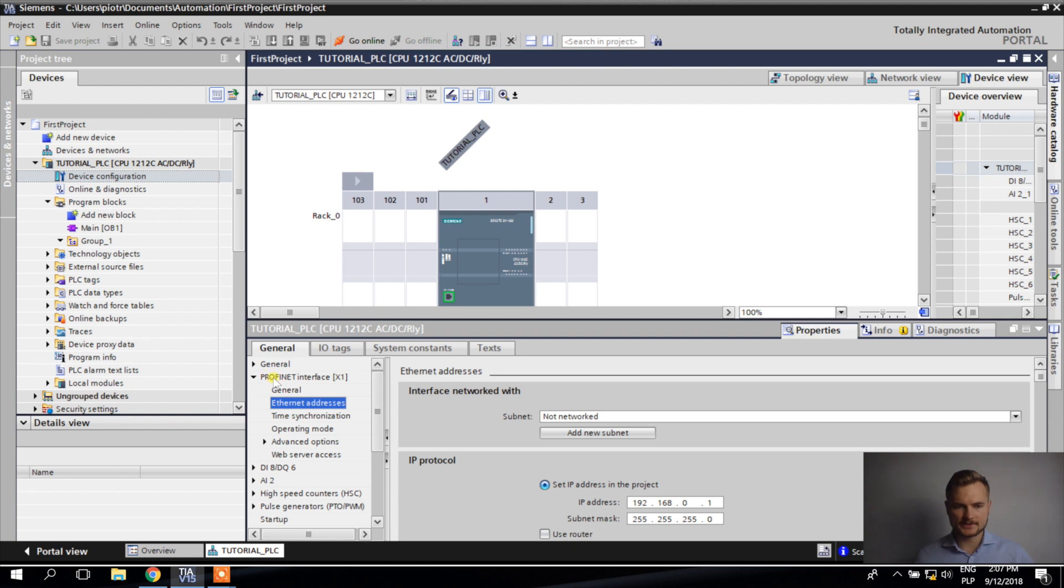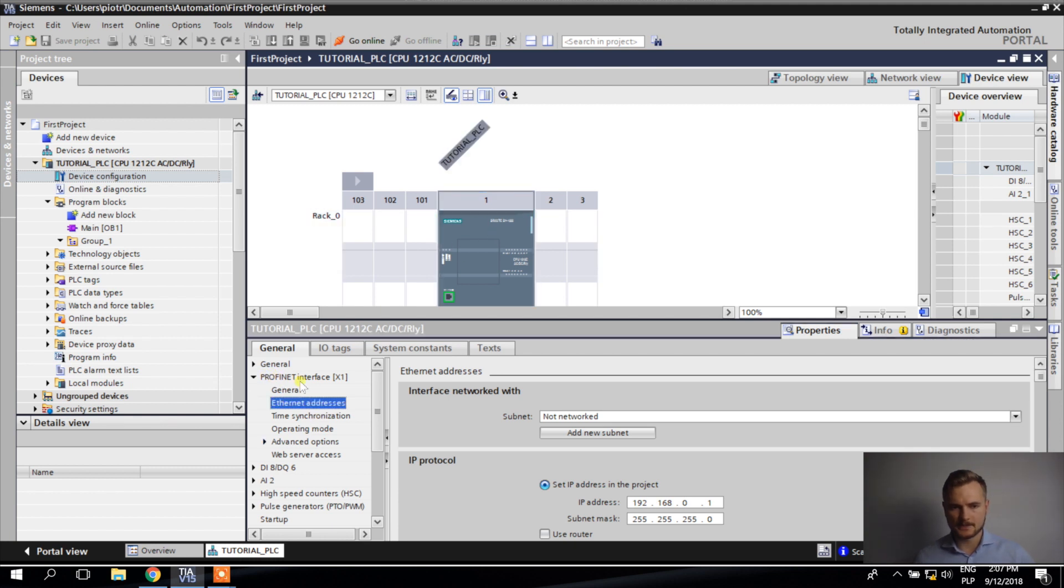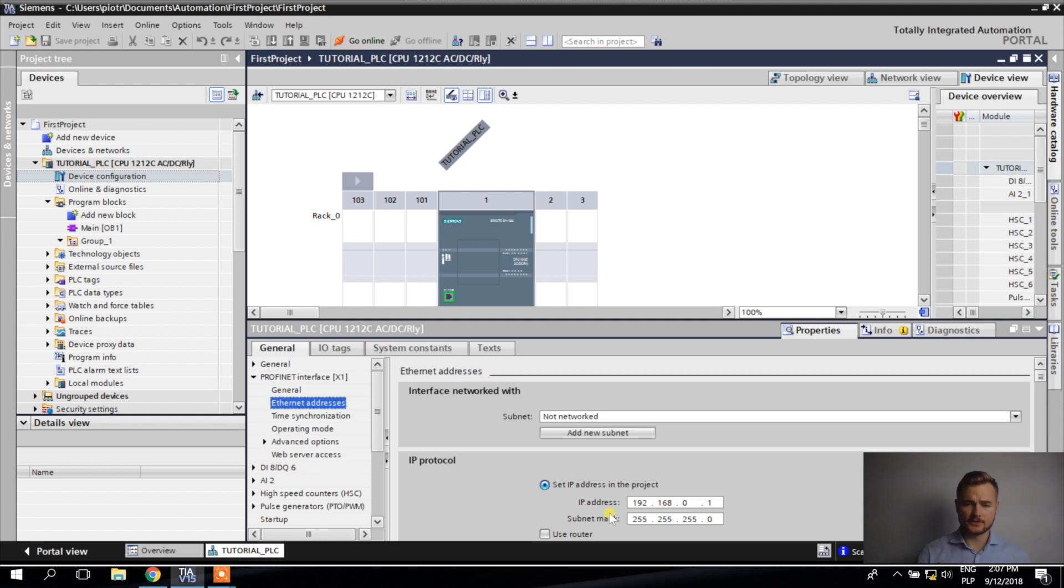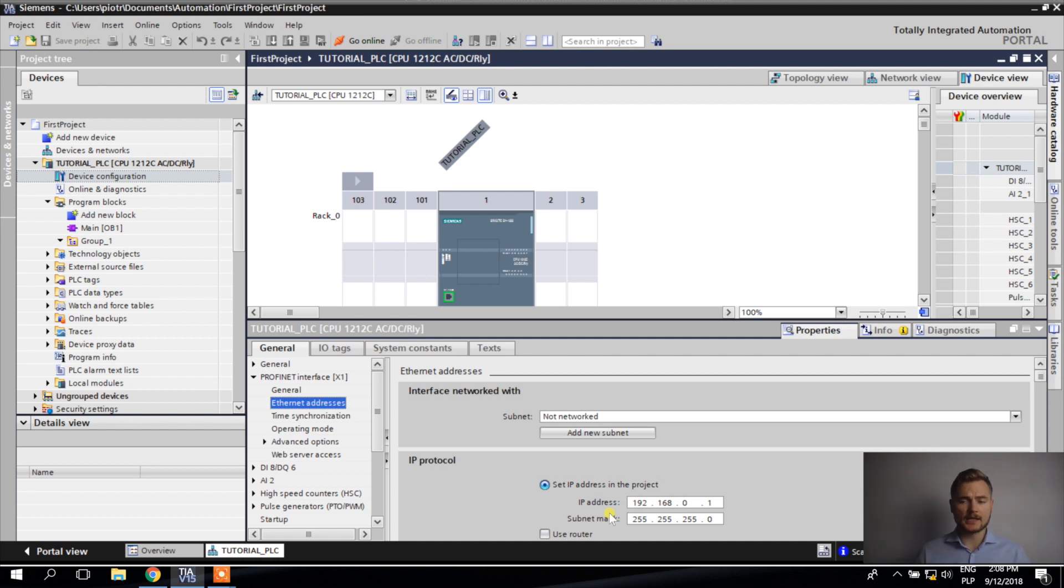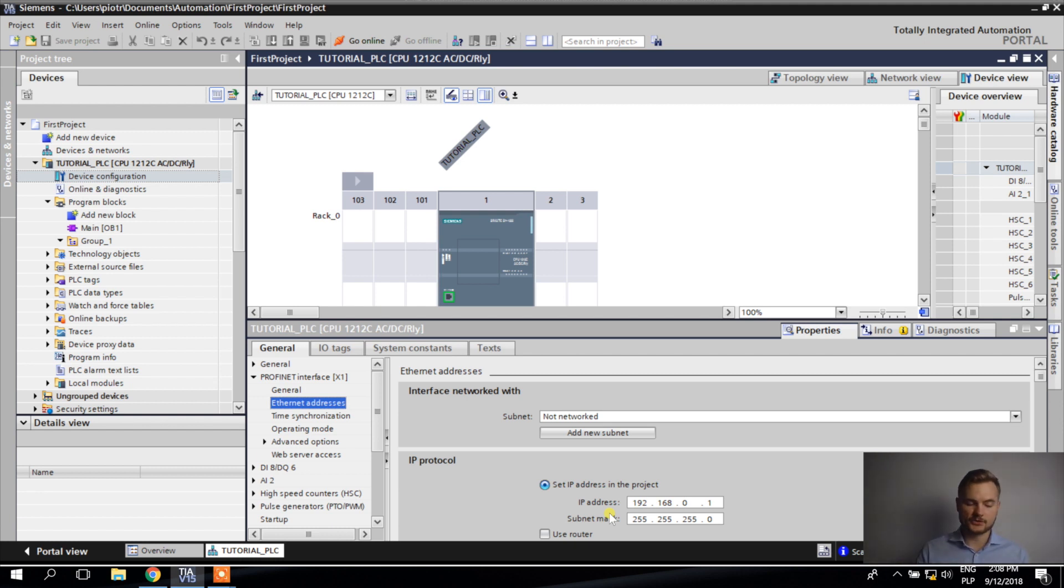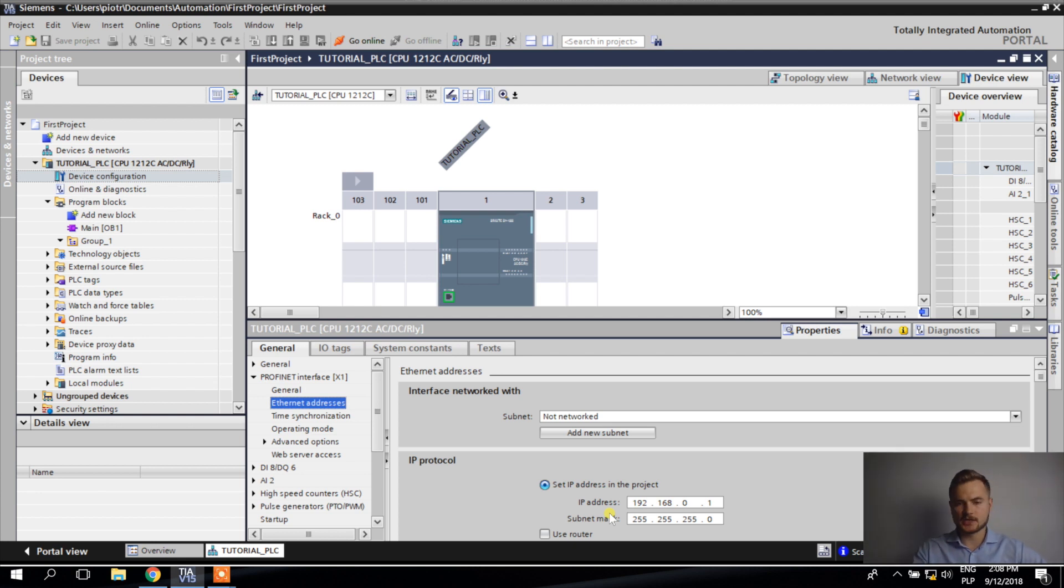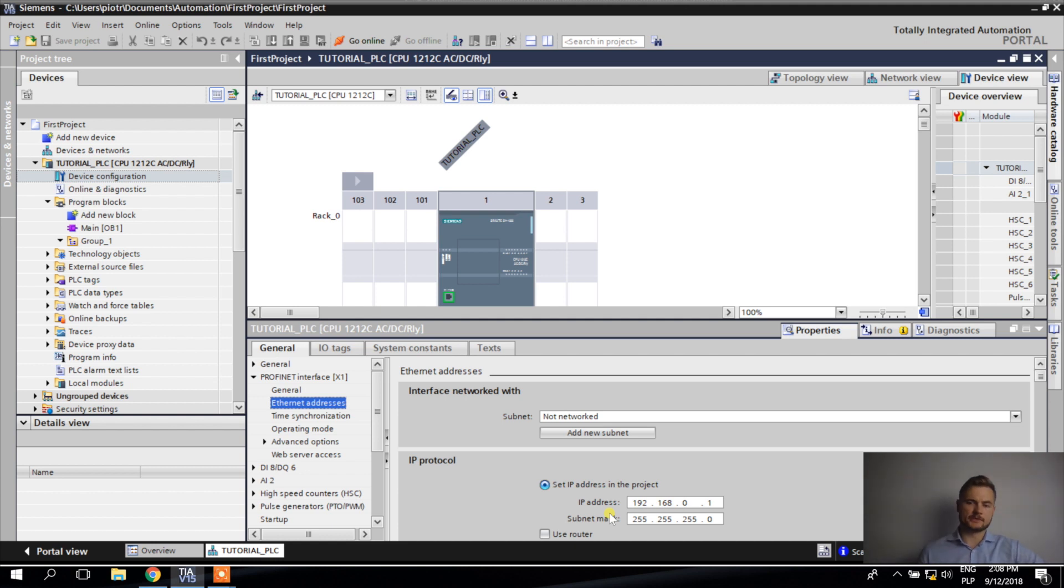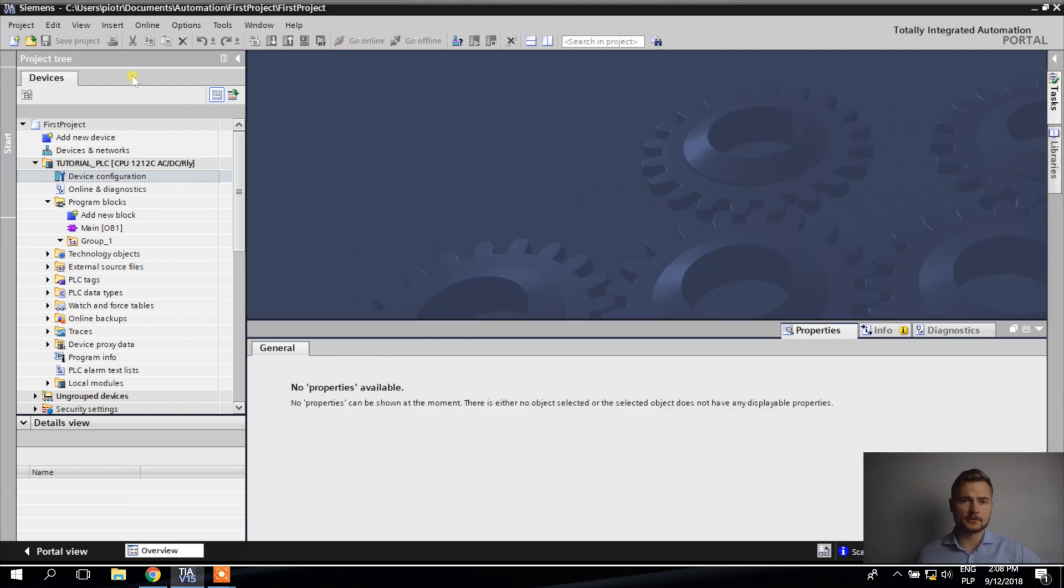It's selected right now, so there's this tab here—when you click on the PLC, there's PROFINET interface where you can set the IP address. The IP address I have here is 192.168.0.1. It was here by default and I don't really want to change it because I don't need to. A lot of customers I've been working for have some IP address pool for PLCs, IP address pool for engineering stations where engineers work to make their programs. It's good to know that this setting is here so you'll be able to change it when necessary.